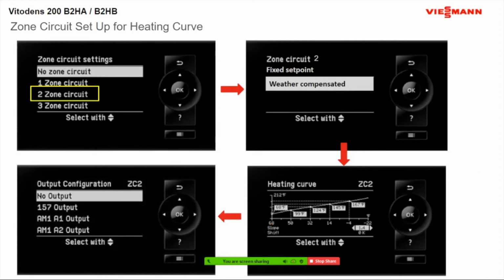For this example here, for the heating curve zone circuit 2, we're going to pick out pump 157. If you added an AM1 module to the boiler, or if you added 2 AM1 modules, you would now see an AM1 module output come up here, and then AM module A2 output come here. So they just added 4 more pumps to this boiler. So you can set up another heating curve, another fixed set point, another heating curve, fixed set point. So this is just a very quick video on how to do this.